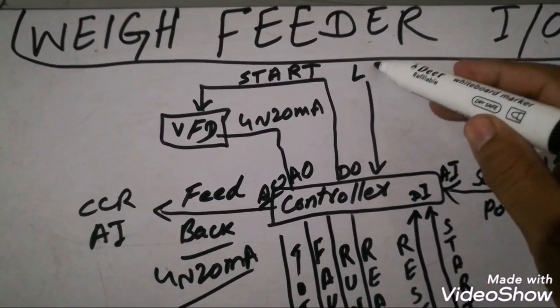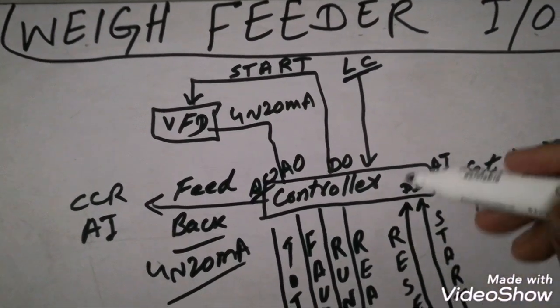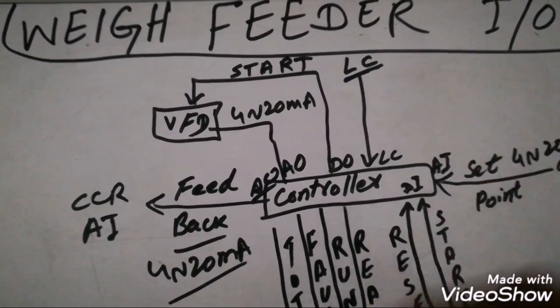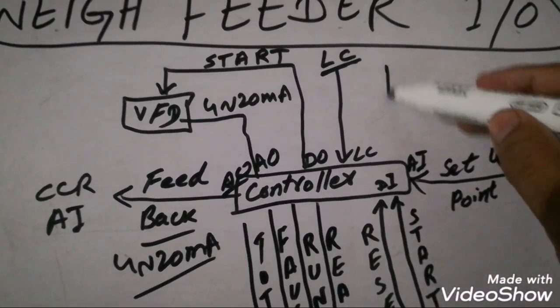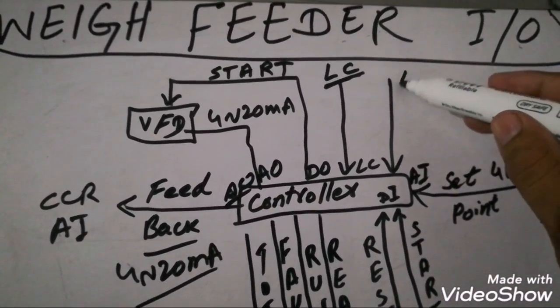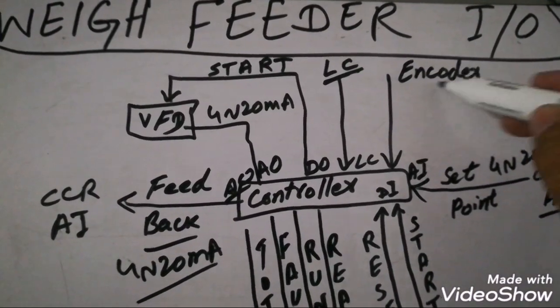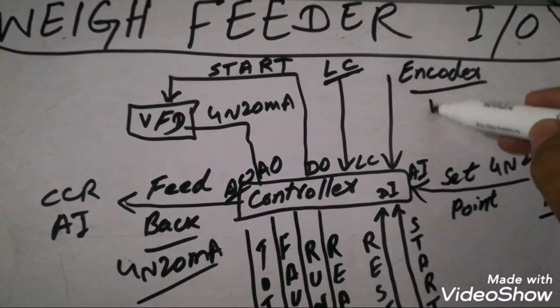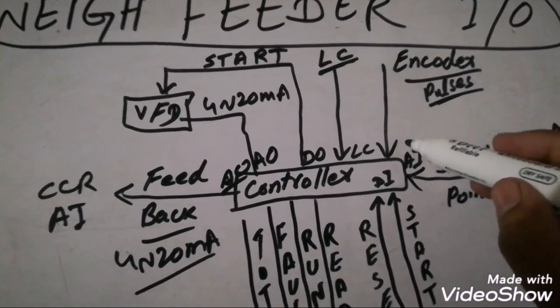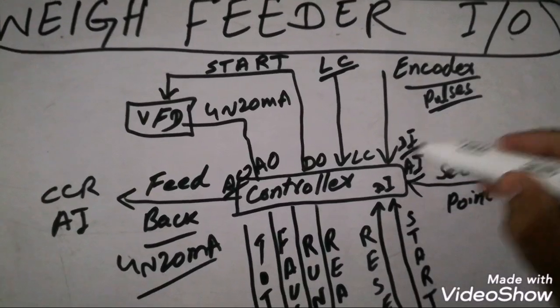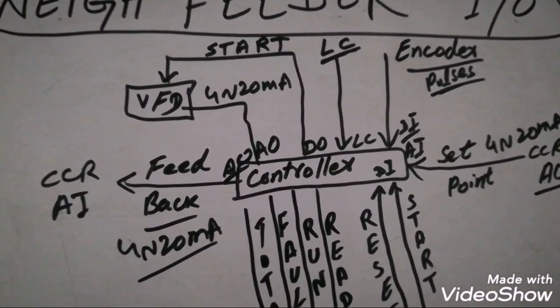The load cell cables are connected to the controller, providing excitation and signal inputs. The encoder input, which is in pulses, is also an input to the controller. This is a digital input on a specific high-speed channel because the encoder pulses are high speed.